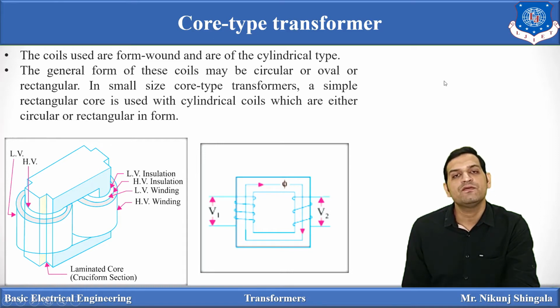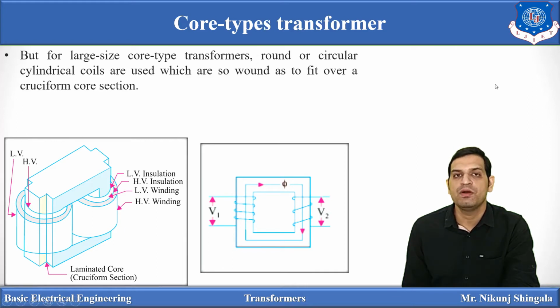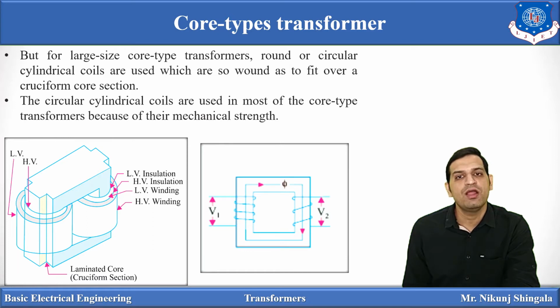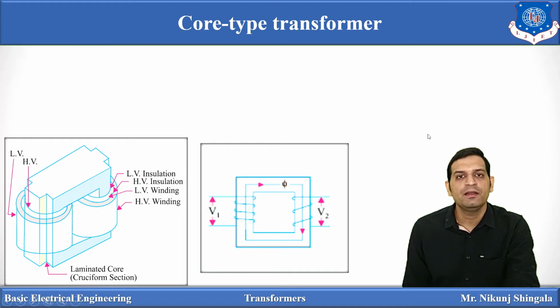In a small size core type transformer, a rectangular core is used and the winding may be cylindrical or in rectangular form, as you can see here. For a large size, high voltage transformer, round or circular cylindrical coils are used, because circular cylindrical coils provide mechanical strength. That's why they are used in most core type transformers. Here in simple form, you can see this is the core, and this is the primary winding and the secondary winding, which are placed on opposite limbs or legs. These are the limbs of the transformer and this is the yoke of the transformer.